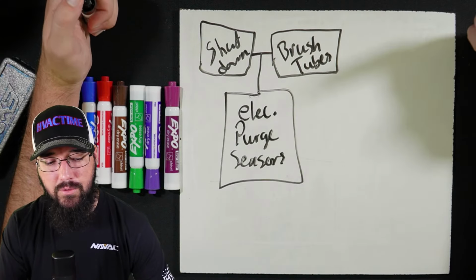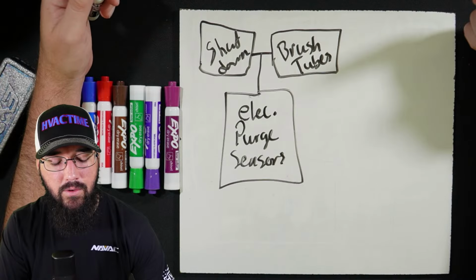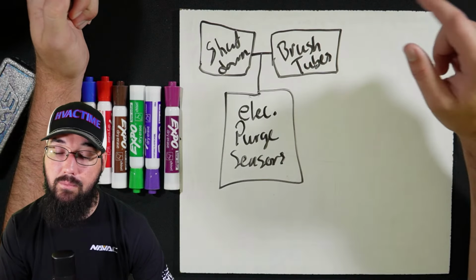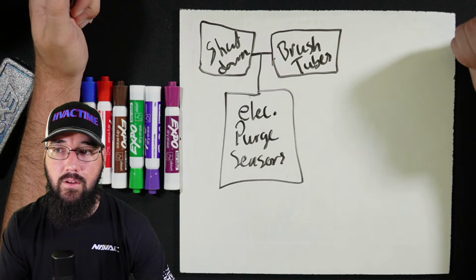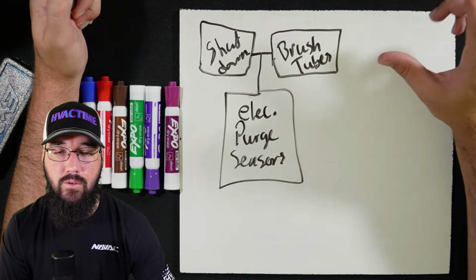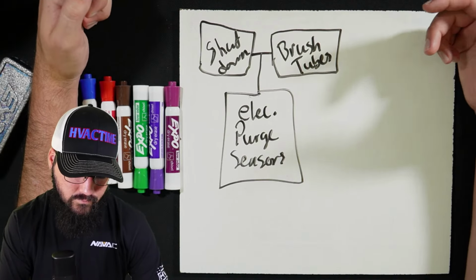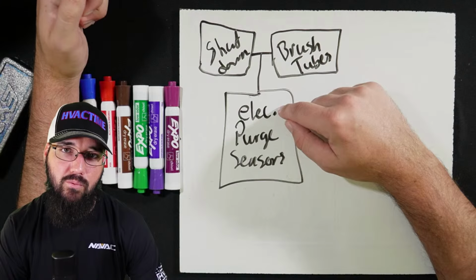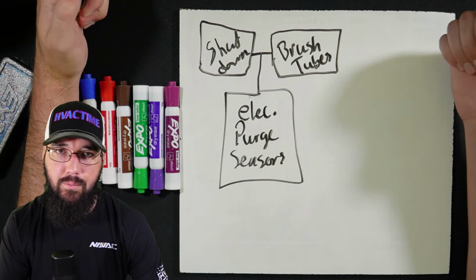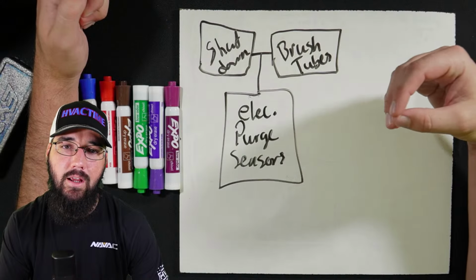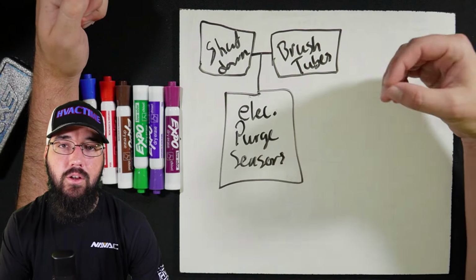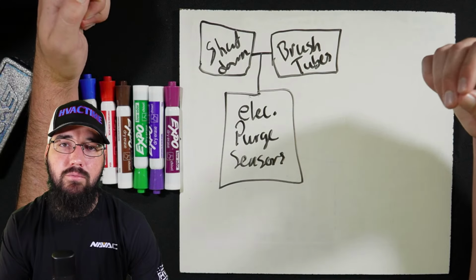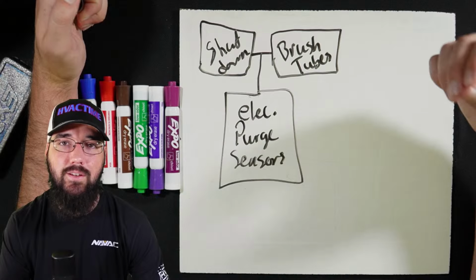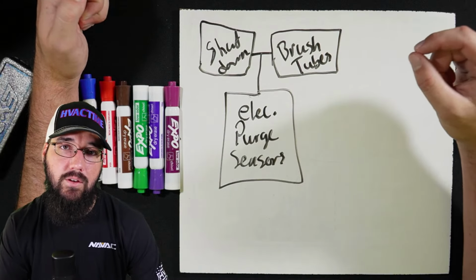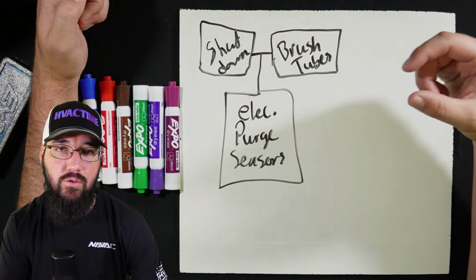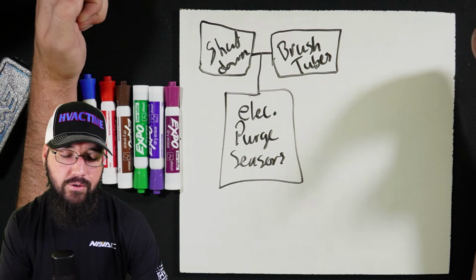Those are refrigerant cooled drives, so we don't have anything on the drive cooling to really worry about, except for the air cooled drives. Those we need to have the little filters and stuff checked, make sure the fans are doing okay, that none of them are locked up. So when I say electrical, that's what I'm referencing, the controls and starter panels, really going through those in detail. And I am one that trains on, we touch every terminal. Every terminal should be checked for its tightness, its connection, nothing's loose. We don't have a wire that's getting hot and maybe wiggling out of its terminal point, anything of that nature. None of that should be happening.